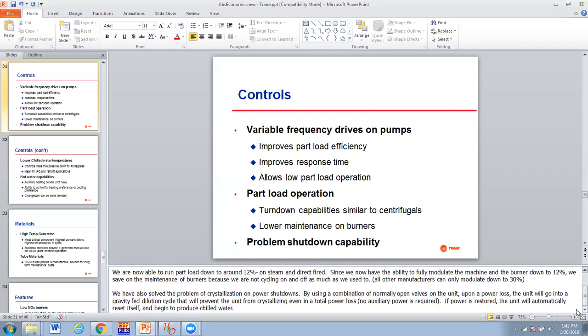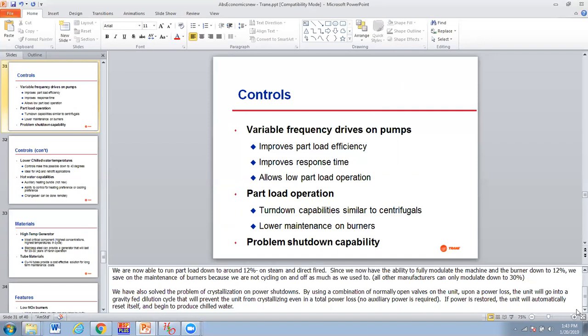Since we now have the ability to fully modulate the machine, its burner, down to 12%, we save on maintenance because we're not cycling the burners on and off as much as they used to. They claim other manufacturers can only modulate down to 30%. These slides are probably a little bit dated, so I'm not sure if that's still true or not. That would take some market research to figure out.